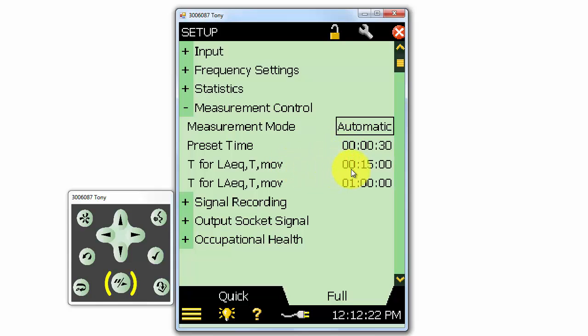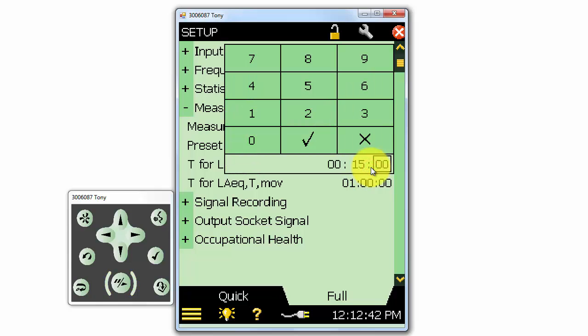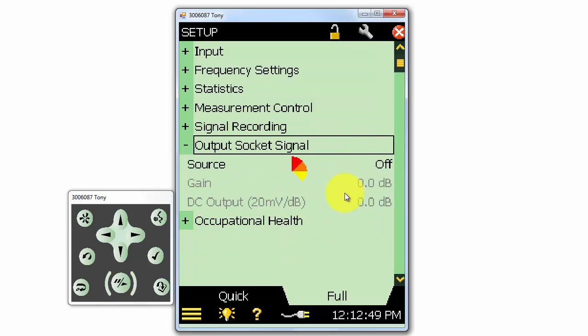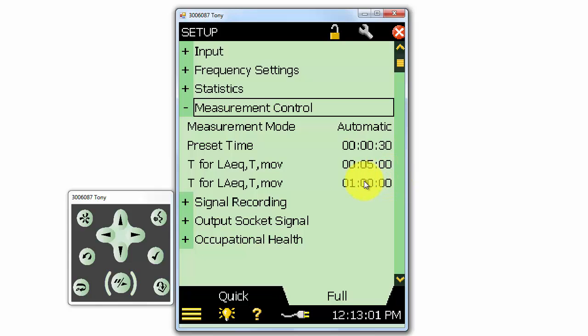The T values are for the moving LAEQ. These will give us a rolling 15 minute A weighted average. It allows us to find the loudest 15 minute portion of any measurement. We can change the time if we want to use something other than 15 minutes. For example, we could select 5 minutes. There are two selections here, because we could have two of these rolling averages running in parallel, with each having their own time interval.